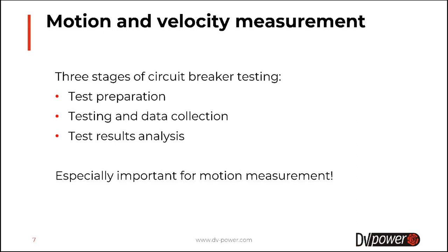Generally speaking, there are three stages of circuit breaker testing: test preparation, testing and data collection, and test results analysis. This procedure is especially important for the motion measurement because actually the biggest task in the field is to mount the transducer in a convenient place in the circuit breaker mechanism.